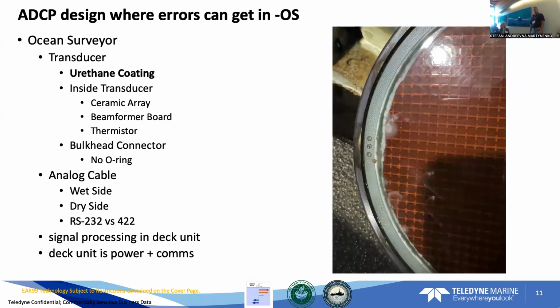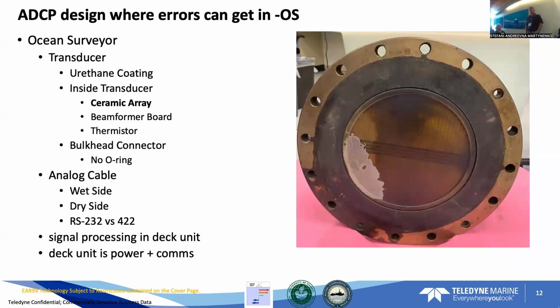Some of the failures on Ocean Surveyor could be the urethane coating. You could have a failure, a bubble of urethane, but that shouldn't happen because it would fail quality inspections on the way out. But if you had biofouling growth in there, or somehow if you didn't have an acoustic window and the urethane got stripped off or pressure washed off or sanded off or something, there could be a failure inside the ceramic in the array. So you have these 4 traces on the board, and you can kind of see the waffle shape for the ceramic for the phased array. You have burnt traces right there. So the ceramic array failed on that one.